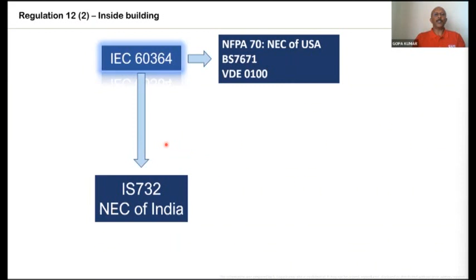The regulation says you must follow the NEC of India or the code of practice. Worldwide, wiring rules come from IEC 60364 - followed by Americans, British, Germans, French, and all over Europe. The equivalent standard in India is IS 732 and the National Electrical Code of India. So every electrical installation, for an HT consumer or where you have your own transformer, must follow the NEC of India and IS 732 within the building.